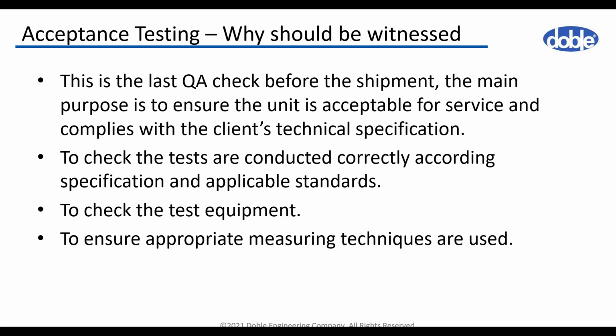Usually, factory acceptance tests are witnessed by an inspector, not only to verify that all the tests scheduled are conducted, but also to perform the last quality assurance check. The manufacturer should demonstrate the unit is acceptable for service and complies with the customer's technical specification. The inspector needs to determine if the manufacturer performed the tests correctly, which is very important, according to specification and applicable standards, using appropriate measurement techniques and suitable calibrated equipment.